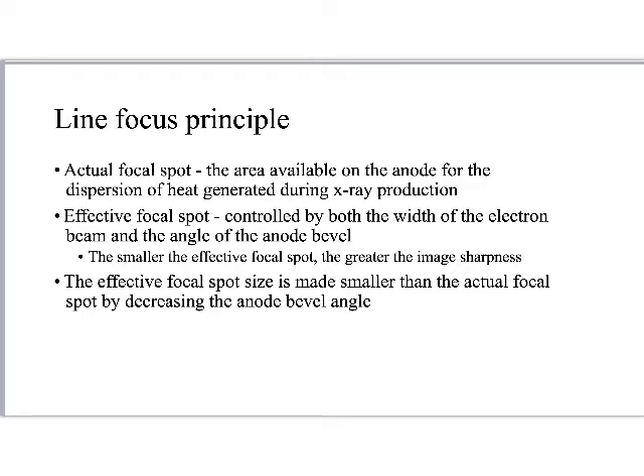Don't get thrown off by that. If you remember, the anode is circular in shape, so if the anode is spinning, imagine almost like a record — there's going to be a track around the anode that distributes the heat across all these various focal spots. The electrons are lazy though, so they're going to find the shortest path to jump from the cathode to the anode. Where they're actually hitting the anode, that is the actual focal spot.